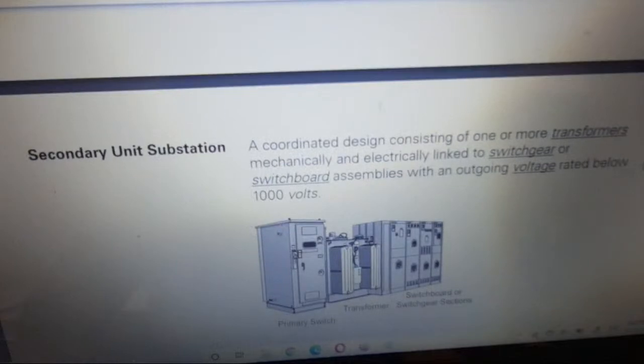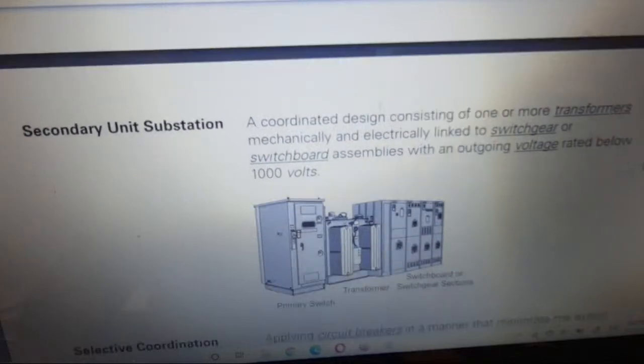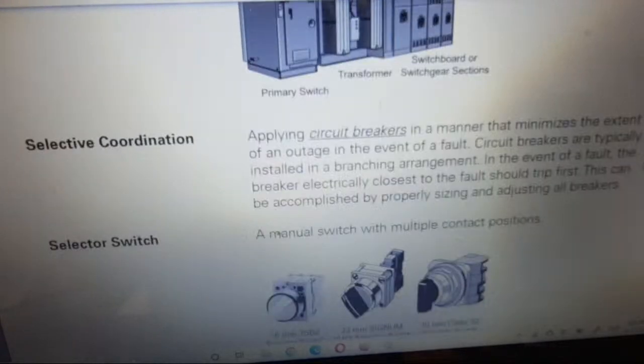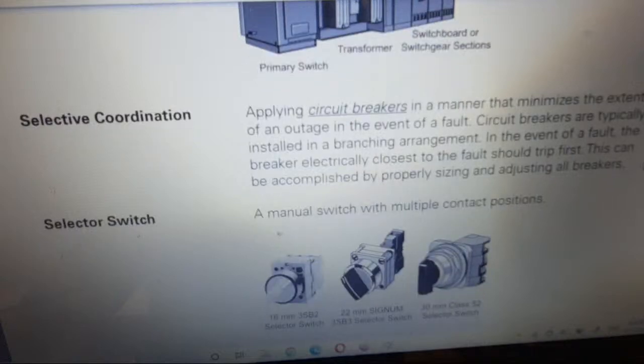Secondary unit substation, a coordinated design consisting of one or more transformers mechanically and electrically linked to a switchgear or switchboard assembly with an outgoing voltage rated below 1000 volts. Selective coordination, applying circuit breakers in a manner that minimizes the extent of an outage in the event of a fault. Circuit breakers are typically installed in a branching arrangement. In the event of a fault, the breaker electrically closest to the fault should trip first. This can be accomplished by properly sizing and adjusting all breakers.